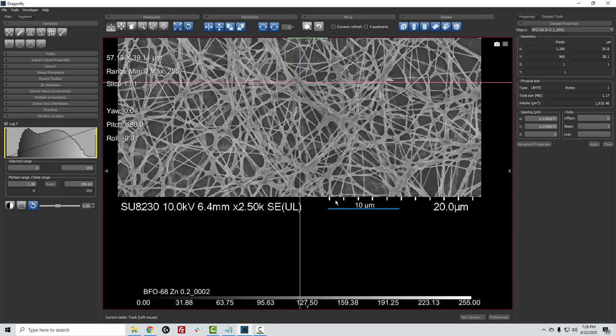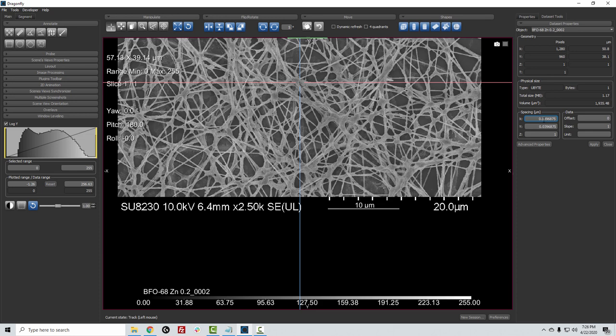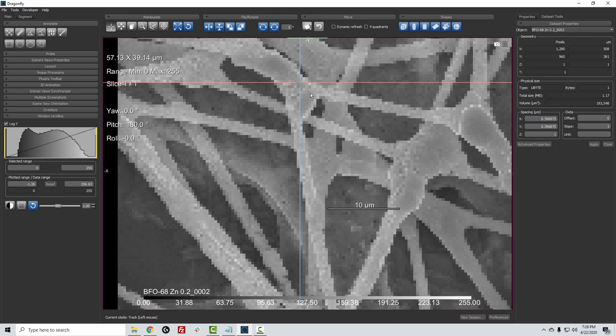Now, if we look, we can see that what should be 100 microns is being interpreted as 10 microns. So, this pixel size is not correct either, but we can tell that it's off by a factor of 10.